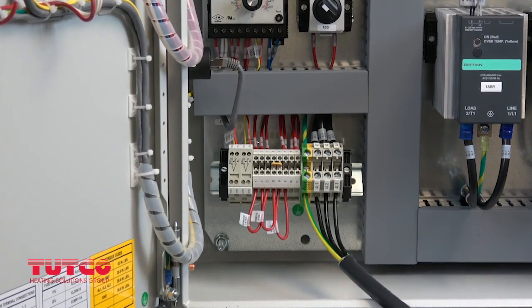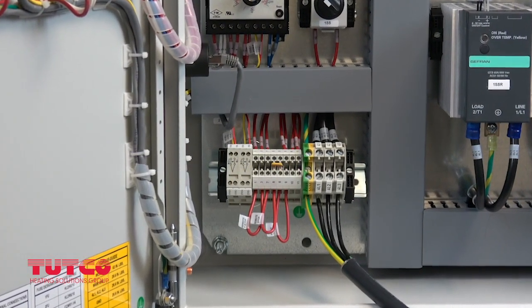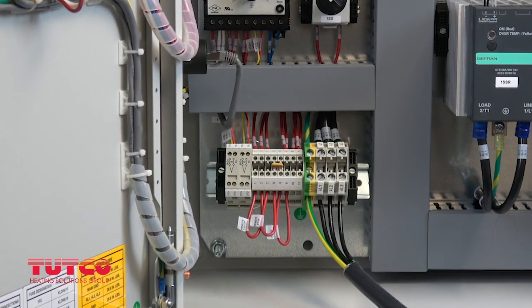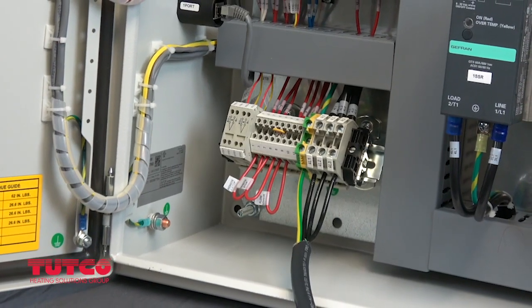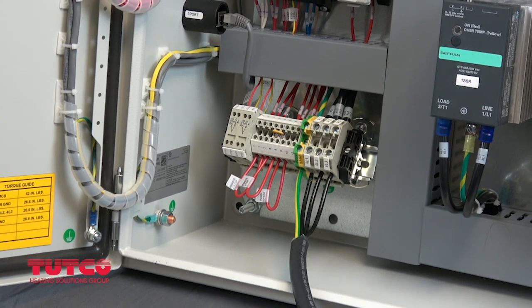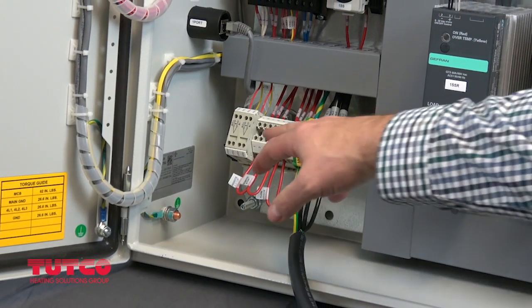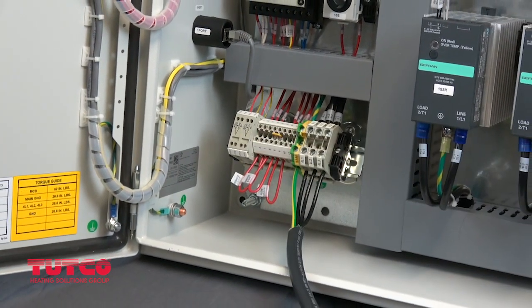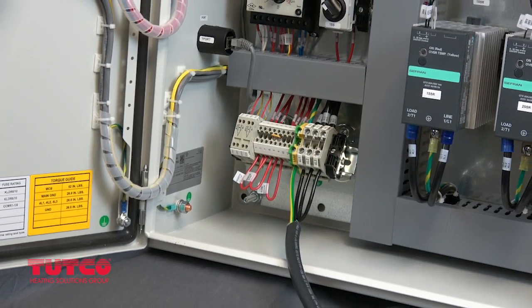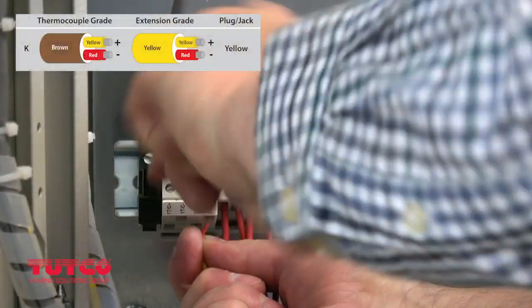There are 2 thermocouple sensor blocks. They are labeled 1TC and 2TC. 1TC is for your high limit temperature sensor connection. 2TC is for the process temperature control sensor. The left terminal is positive and the right terminal is negative.